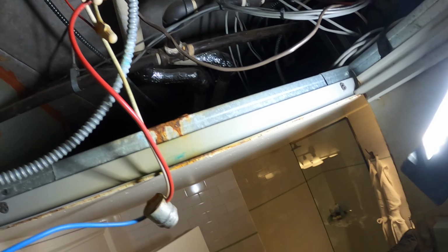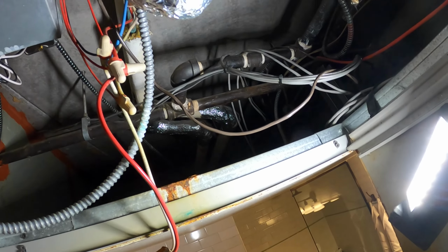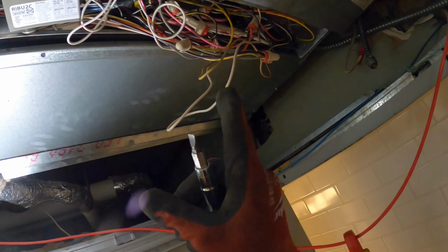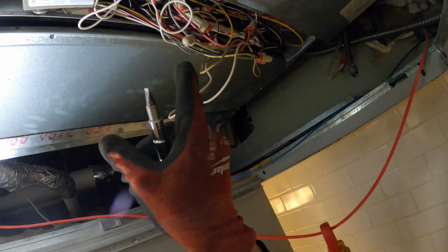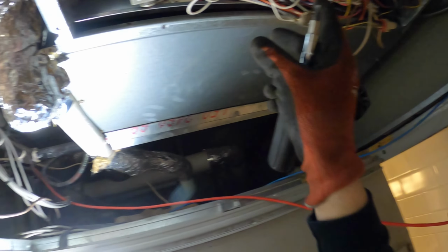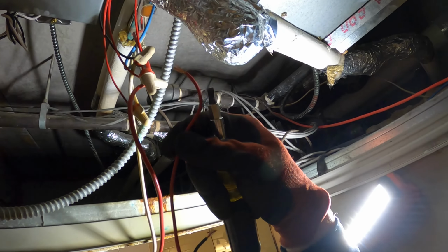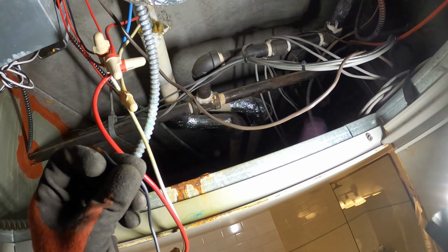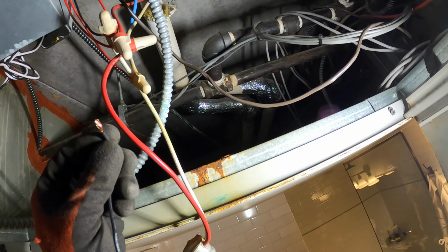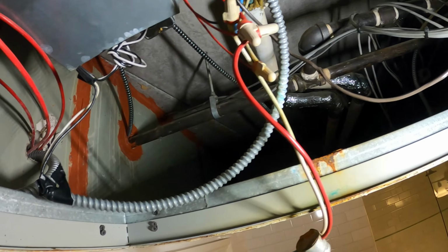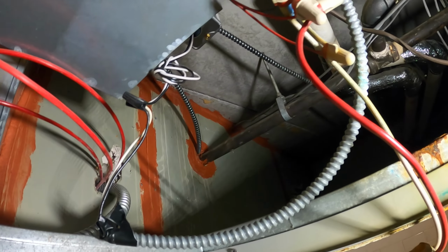We're gonna put the red common, which gets connected to the wire coming from the thermostat. The 120 volts, the yellow wire, comes in and feeds the red common. It senses the pipe is cold and sends power, the 120, out of the black wire to feed our actuator valve.